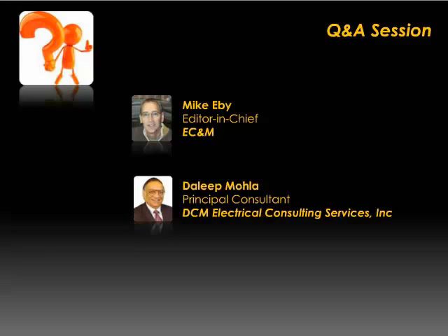All this helps a lot in your risk analysis. If you can convince yourself and convince the management that, hey, the system is okay, if the first fault happens, which is 90 to 95% of the time, we are limited to 5 amps or less. What is the probability of a second fault happening, while we are doing that? So OSHA does not restrict blanketly. OSHA wants the employer to demonstrate that it is necessary and it can be done safely. So high-resistance grounding is a very effective tool to reduce the risk.